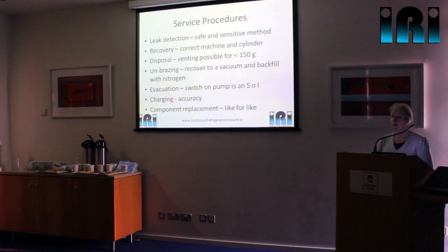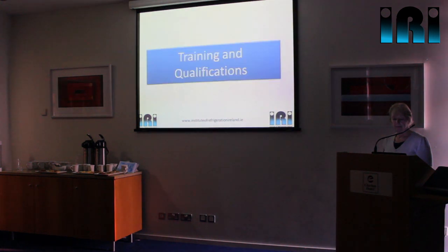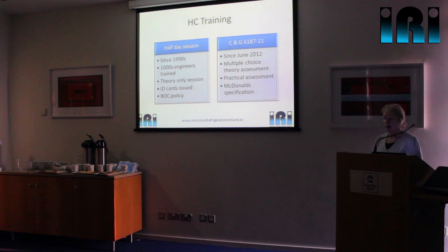When charging the systems, because of the lower density the charge weight is less, so we have to be really careful about how accurately we charge systems — that's a challenge. When replacing components, it's important that we replace like for like on the electrical components because a lot of them are different to standard. On the training and qualifications side: we've been running this half-day session since the mid-90s, with several thousand engineers through it. It is a theory-only session, but it started because when BOC launched hydrocarbons into the UK market they made it a sales policy that restricted sales of the hydrocarbon refrigerant to engineers who had attended the session.